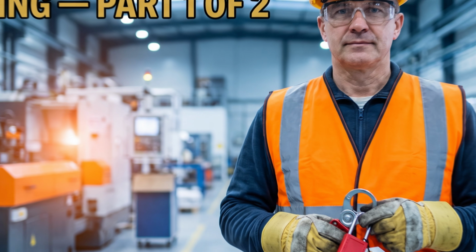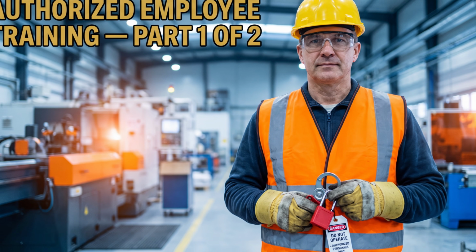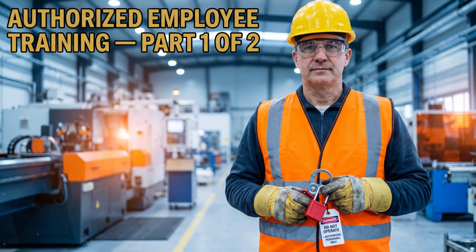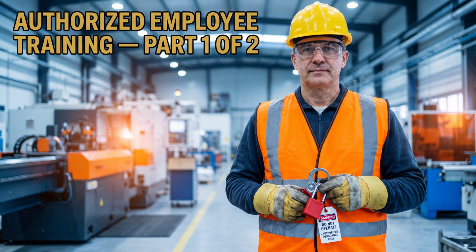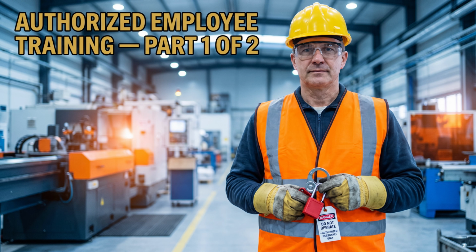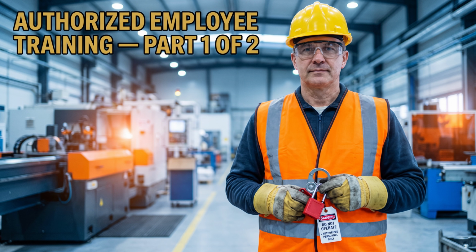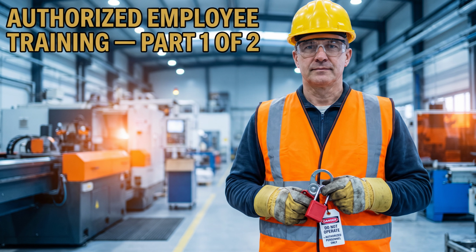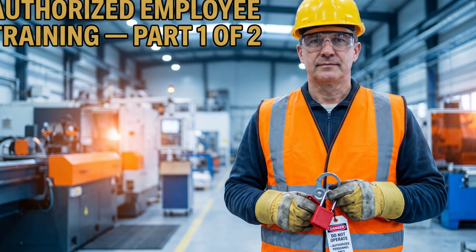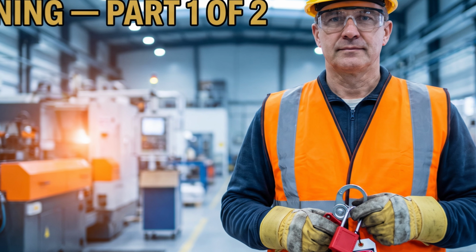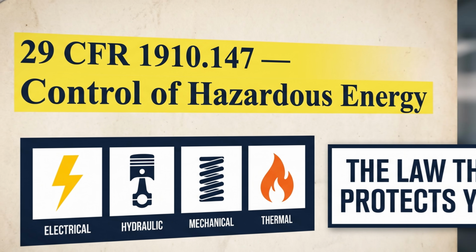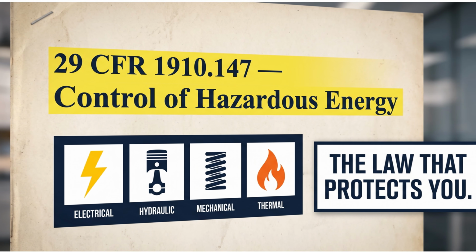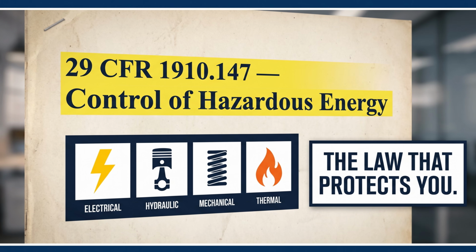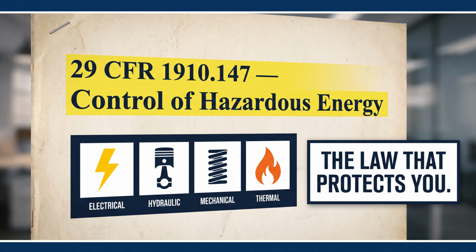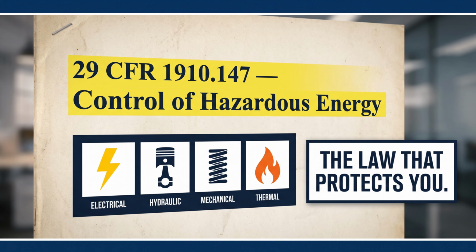1910.147. This training is specifically designed for authorized employees, someone trained to apply lockout or tagout devices to control hazardous energy before performing service or maintenance on machines and equipment. By the end of both parts, you'll know exactly what to do, when to do it, and how to prove you did it right. Lockout/tagout is governed by OSHA Standard 29 CFR 1910.147, the Control of Hazardous Energy standard.